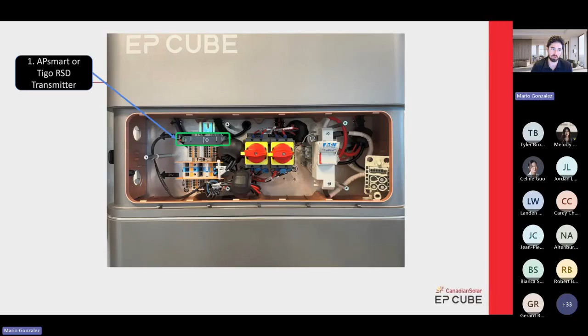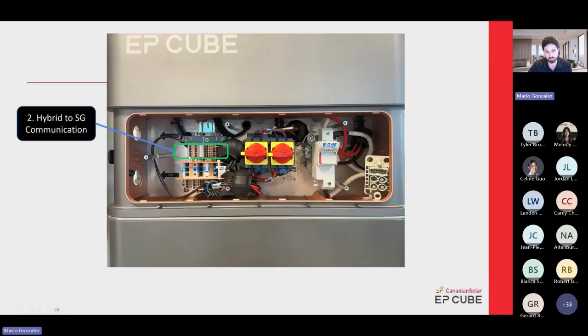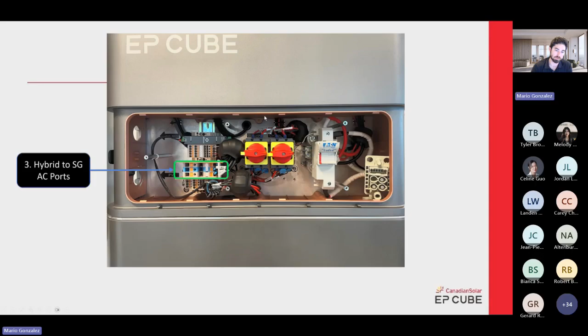And hybrid communication cable. So this is where you would connect the hybrid communication cables coming from the gateway. Again, this is pretty standard and straightforward. It's labeled. Take your time. Make sure your wires match your label terminations. And this is the hybrid AC, the AC ports. This is where you connect basically your 40 amp breaker, and it exports AC energy after being converted from the inverter. The 4 MPPTs, as I mentioned, you have 1, 2, 3, 4 MPPTs per inverter. So disconnect 1 is for MPPT 1 and 2. Disconnect 2 is for 3 and 4.